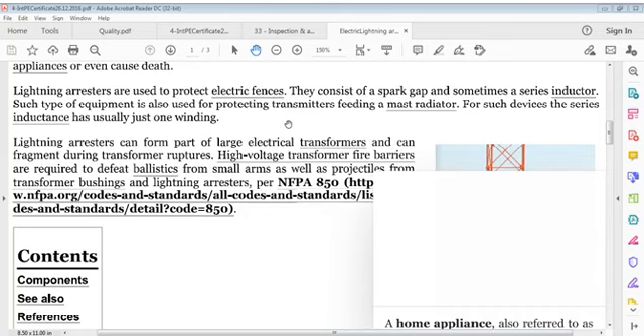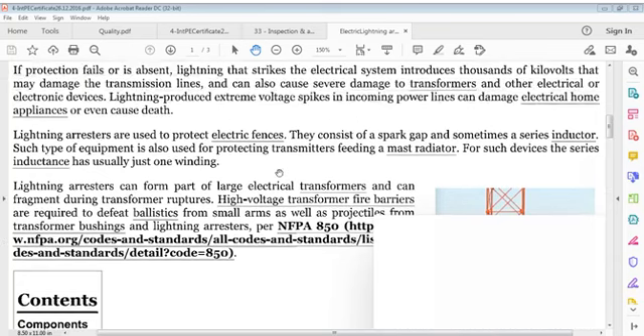Lightning arresters can form part of large electrical transformers and can fragment during transformer ruptures. High voltage transformer fire barriers are required to defeat ballistics from small arms as well as projectiles from transformer bushings and lightning arresters per NFPA 850. So we have seen that.